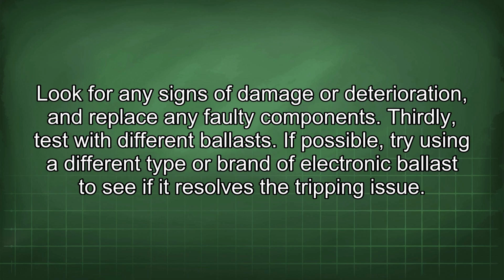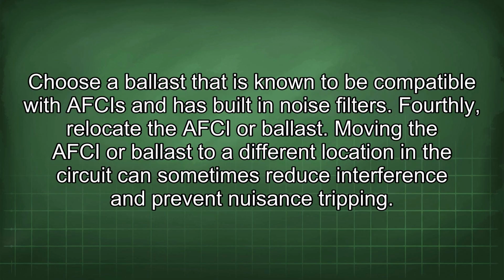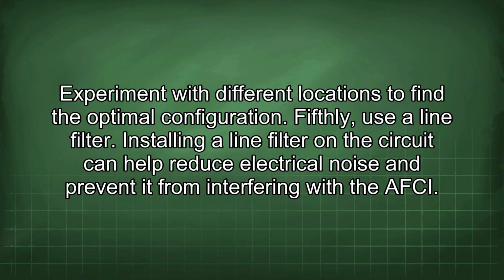If possible, try using a different type or brand of electronic ballast to see if it resolves the tripping issue. Choose a ballast that is known to be compatible with AFCIs and has built-in noise filters. Fourthly, relocate the AFCI or ballast. Moving the AFCI or ballast to a different location in the circuit can sometimes reduce interference and prevent nuisance tripping. Experiment with different locations to find the optimal configuration.